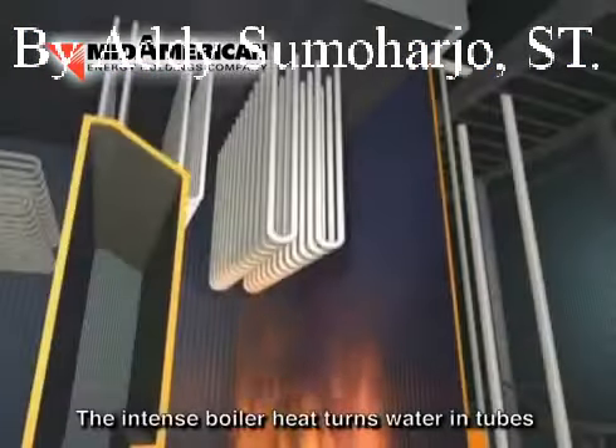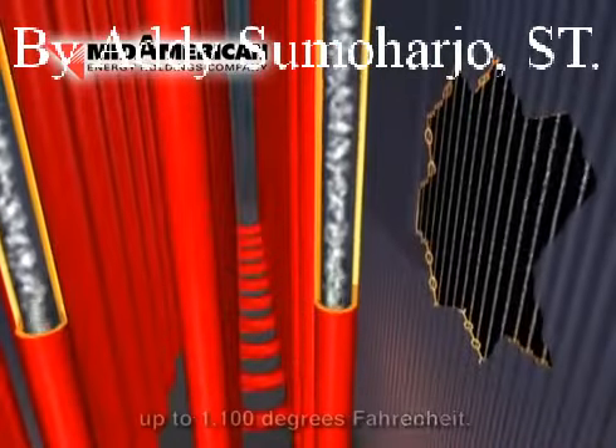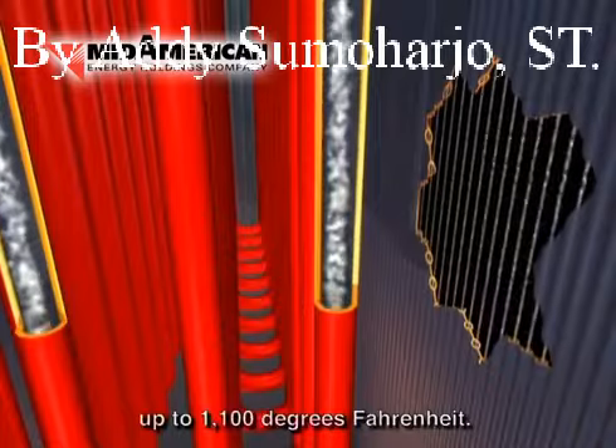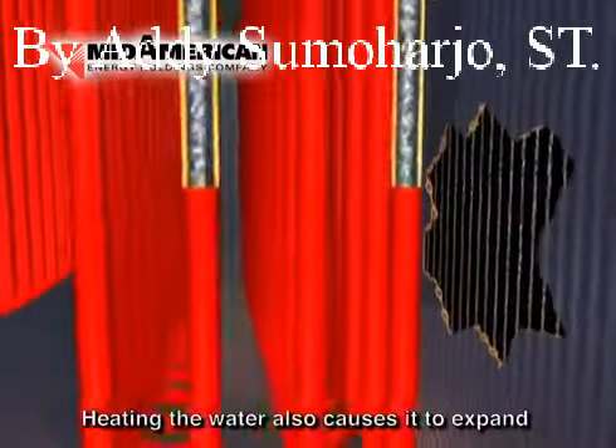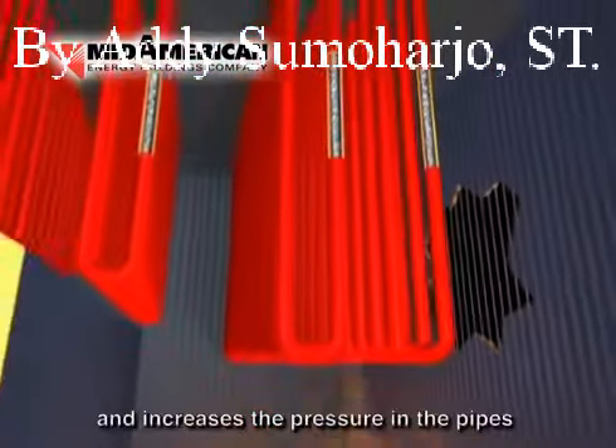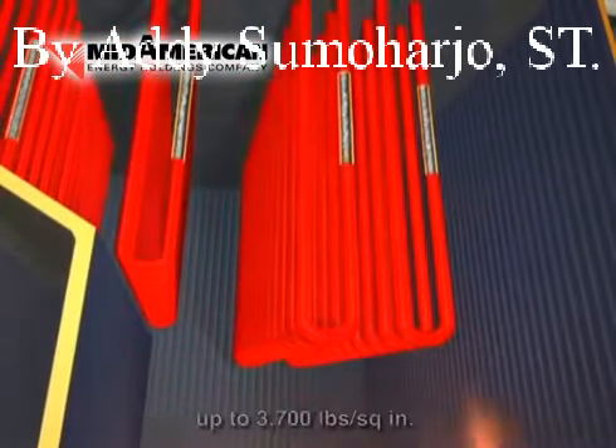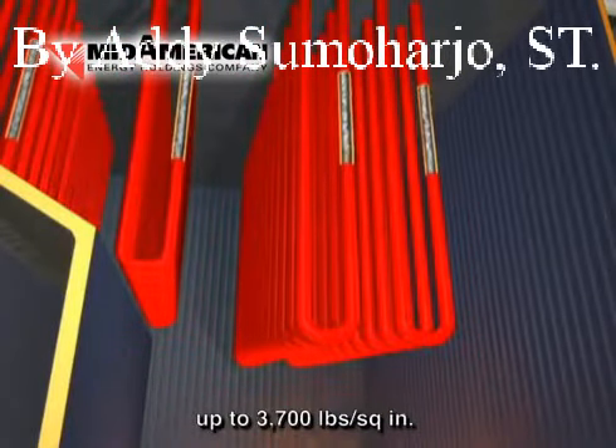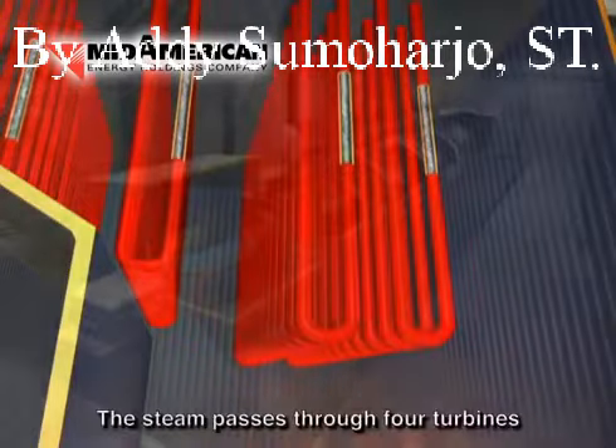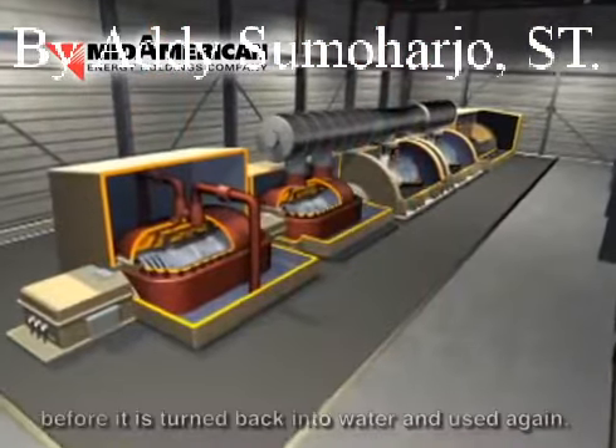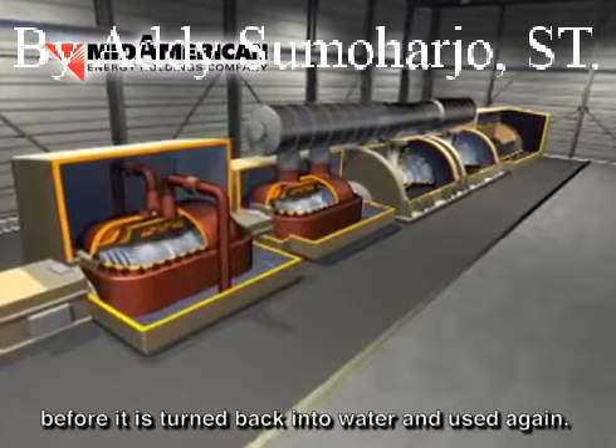The intense boiler heat turns water in tubes into steam that can reach up to 1,100 degrees Fahrenheit. Heating the water also causes it to expand and increases the pressure in the pipes up to 3,700 pounds per square inch. The steam passes through 4 turbines before it is turned back into water and used again.